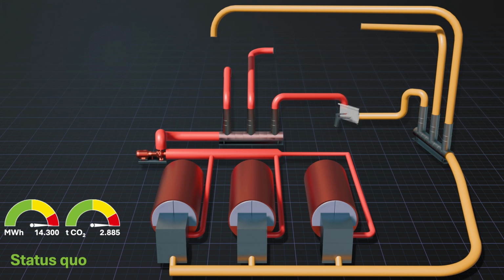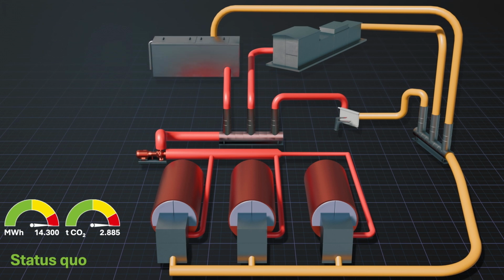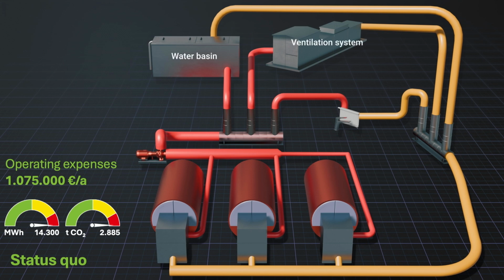Because the plant has grown over the years and new production areas as well as heating surfaces have been added, the current state no longer corresponds to the actual requirements of the heating network. This results in a hydraulic system that no longer functions properly, excessive volume flows, and the associated increase in operating costs. In this example, we want to look at the water basin of the paint shop and the ventilation system.